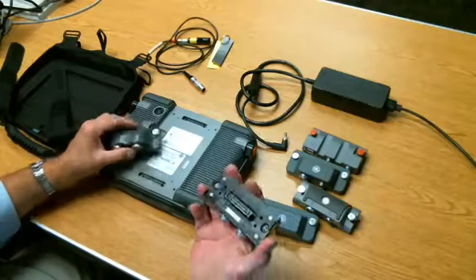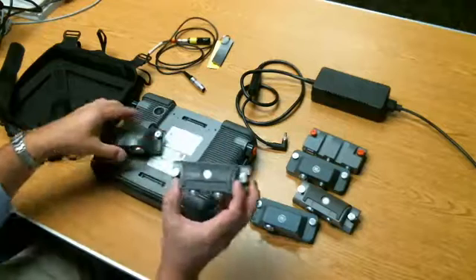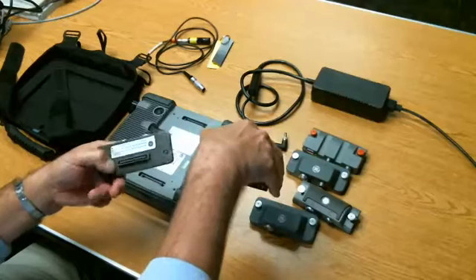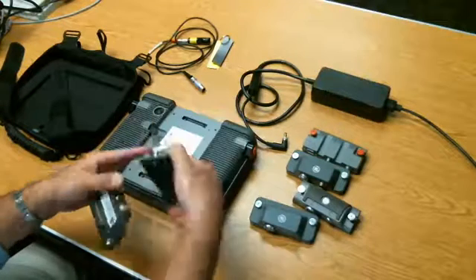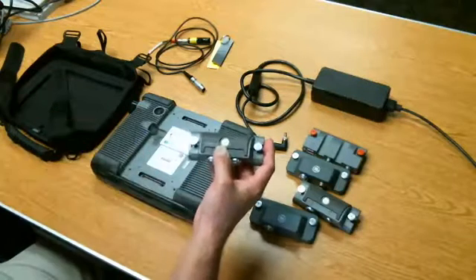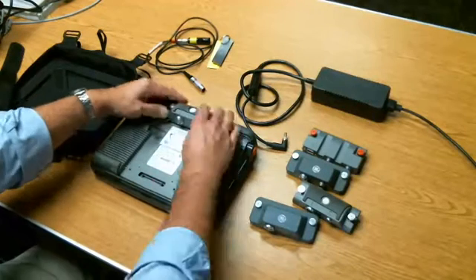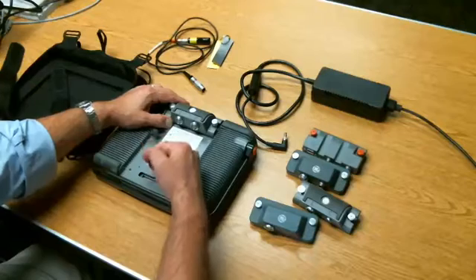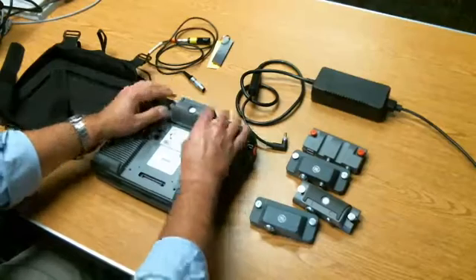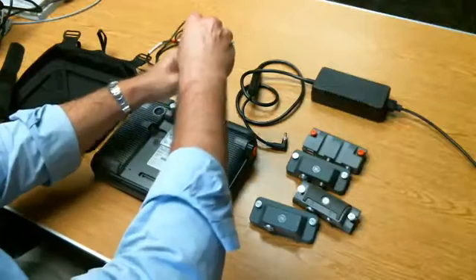The more modern housings have an aluminum base plate and a rubberized exterior, and feature the GE logo in the middle. You can see this has a rubberized base plate where the older one has anodized aluminum — these more recently manufactured modules have a more finished appearance. These modules can actually be plugged on at your convenience, either with the connectors facing the middle, or they can be rotated 180 degrees and attached such that probe connectors come out the top for easier access. We are going to attach ours in that orientation.